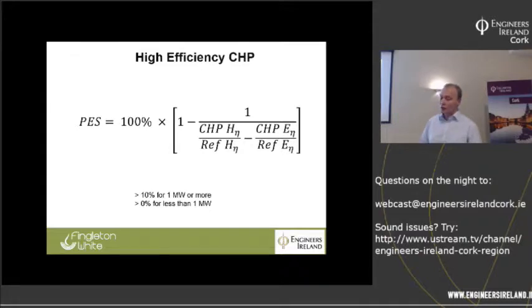And then the CHP electrical efficiency is fairly obvious. You take the electrical output from the generator and divide it by the fuel input. The two reference values then come from a separate regulation, which is published by the EU. To qualify as high efficiency CHP, you need to achieve 10% or more for systems that have an electrical capacity greater than 1 megawatt. And for systems less than 1 megawatt, it's primary energy savings greater than 0%. So if you're less than 1 megawatt, it's not an overly arduous goal, but for greater than 1 megawatt, it's 10%, which is also not too difficult to achieve, as you'll see in the results from the worked example.